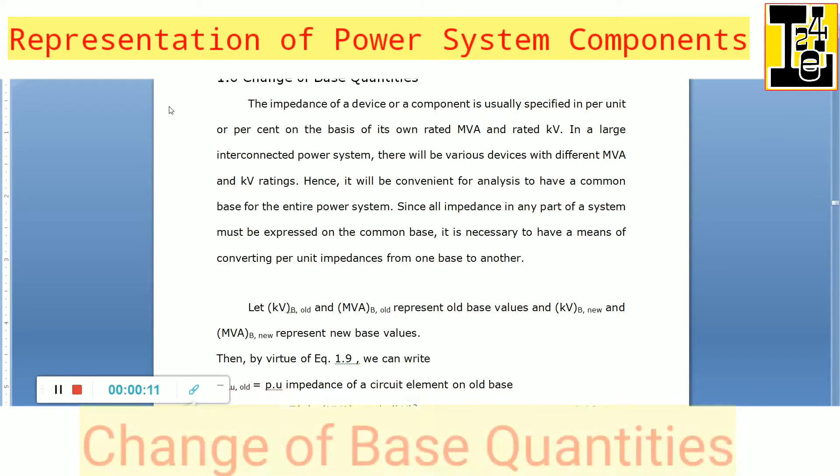The impedance of a device or component is usually expressed or specified in per unit or percent on the basis of its own rated MVA and rated KV. In a large interconnected power system, there will be various devices with different MVA and KV ratings.